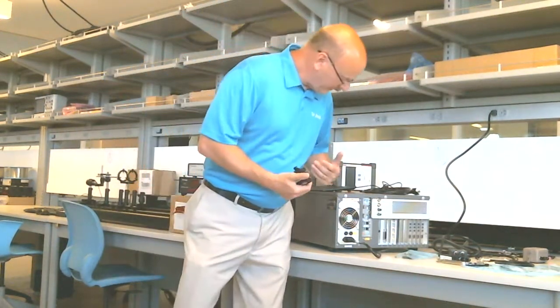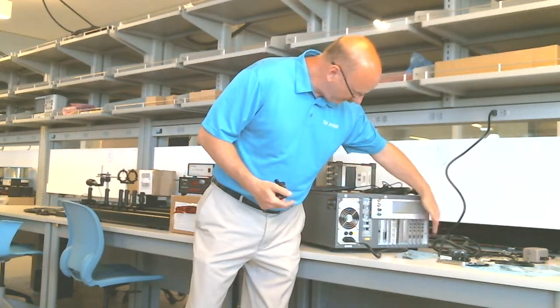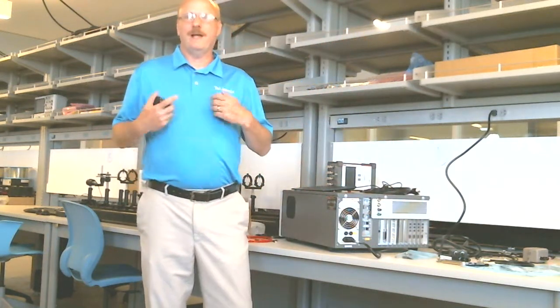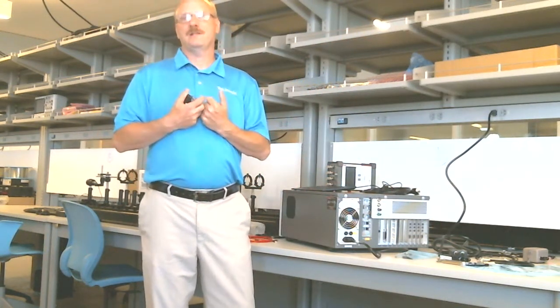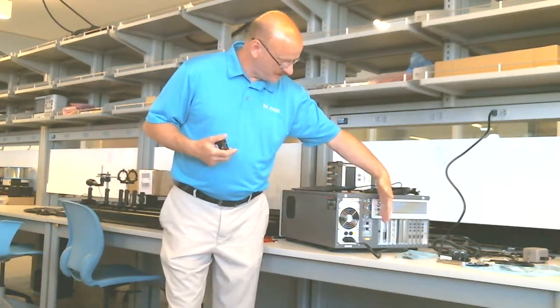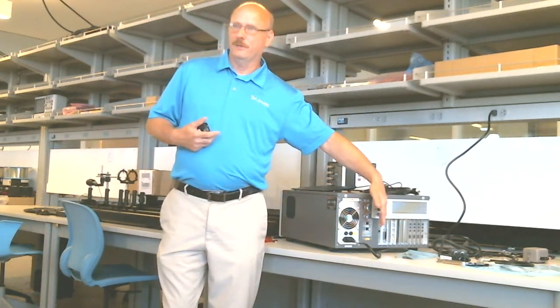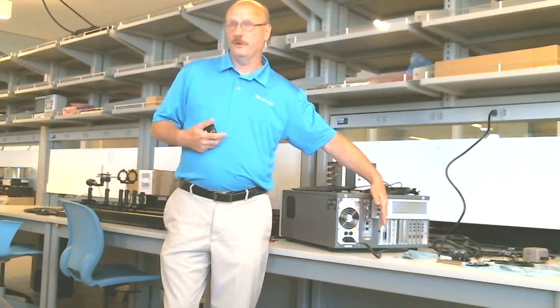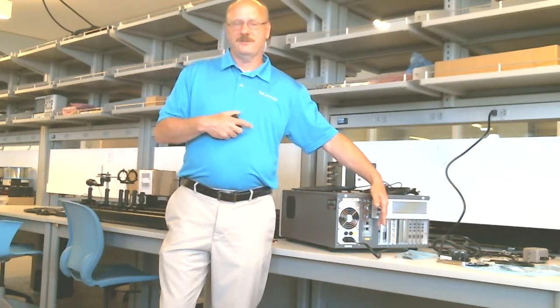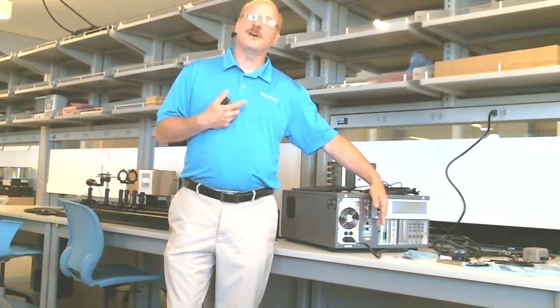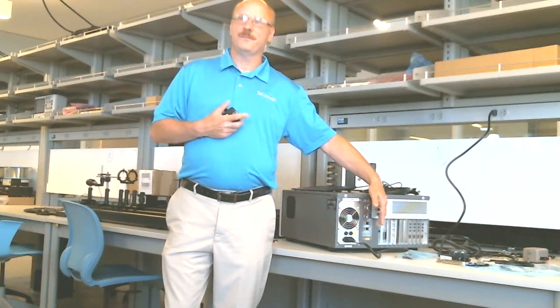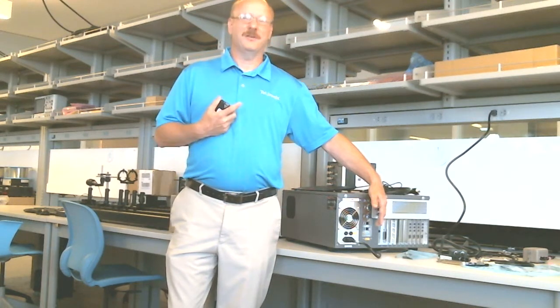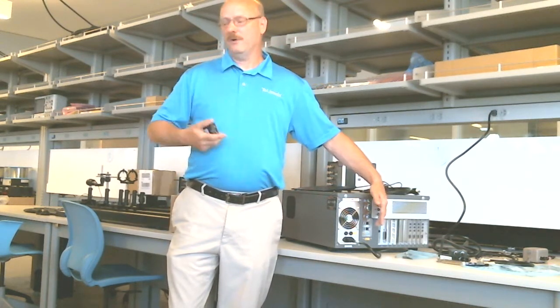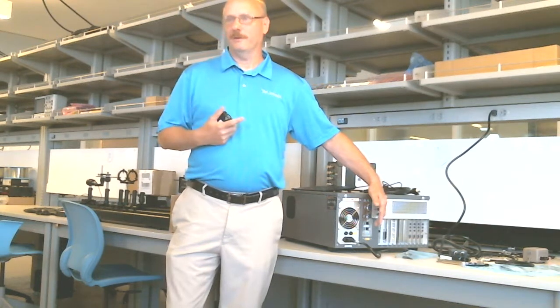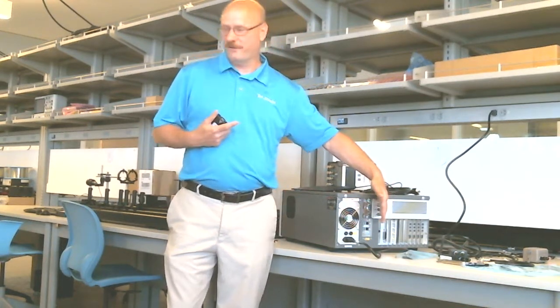We've got 9 slots, and you've got 4 SMUs. In reality, you can do 5 terminal devices, because there's an additional SMU in the chassis, which we call the ground unit. It can only source 0 volts, that's all it can do. It can't measure, it can't do anything else, it's just for making a ground. But you're always going to have a ground in your device anyway, so you can use that as a 5th channel.